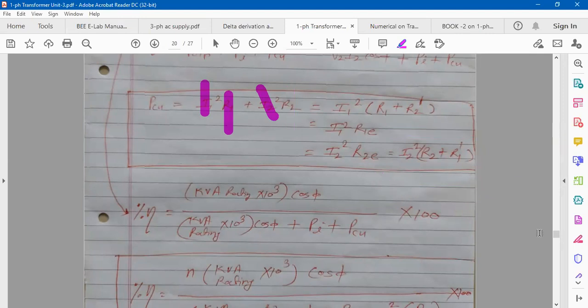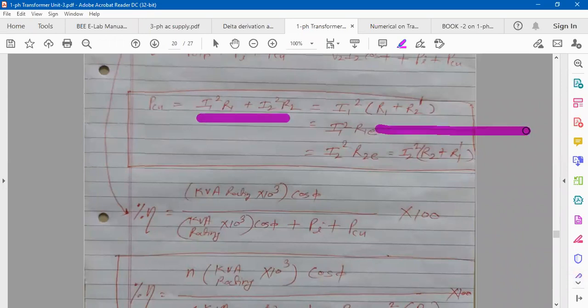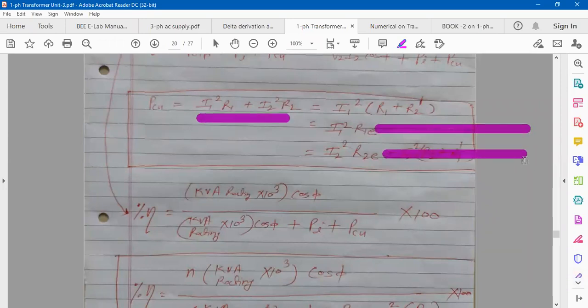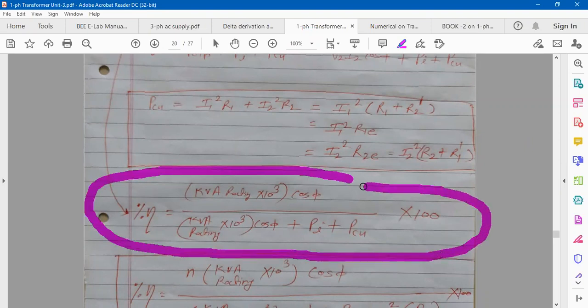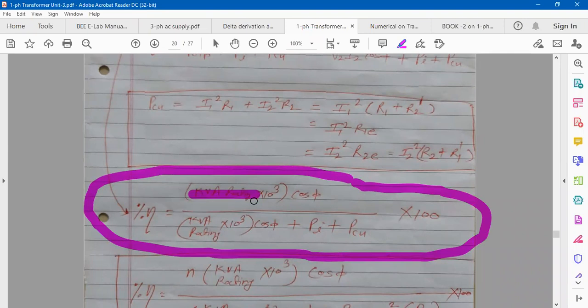Out of the three formulas, any one can be used to calculate copper loss once you know R1, R2, V1, V2, and KVA rating. The KVA rating on the nameplate — suppose 1 KVA, 110V/220V — is the full load KVA rating. But as you go on changing the load on the transformer, I1 and I2 change, so KVA rating also changes.